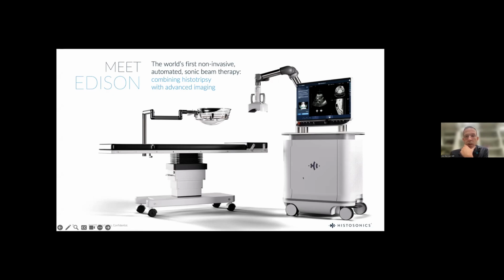The generator creates very high voltage that flows up through the robotic arm into what we call the transducer. Inside the transducer, we have piezoelectric elements that are activated and generate very high ultrasound beams. Those beams coalesce, similar to radiation, into a single isocenter, where it creates a very high pressure that activates water vapors inside of the tumor cells, which expand and create bubbles. As those bubbles expand and contract, it shears tumor cells, immediately lysing them and creating an acellular lysate.